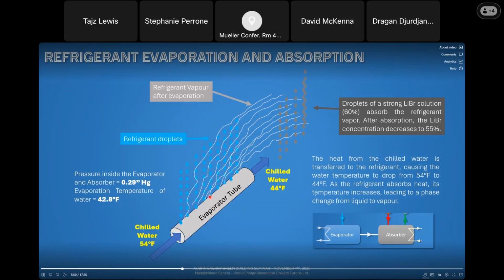By evaporating, we extract latent heat from the chilled water and we cool it, like in this example, from 54 degrees to 44 degrees. This happens thanks to the low evaporation temperature, because at the pressure of 0.29 inches of mercury, the evaporation temperature of water is just 42.8 degrees. Then you can see here on the right side the concentrated lithium bromide solution droplets absorbing the refrigerant vapor.